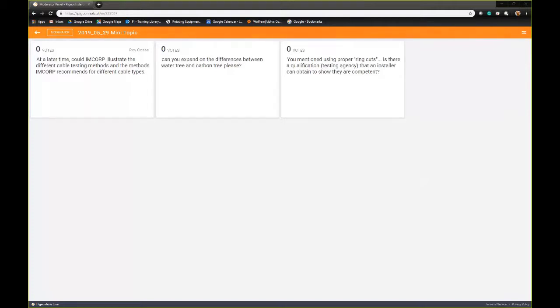In that 60-second time frame, we can capture all the information, a foot-by-foot profile of that cable, and tell you if it's good, if it's bad. We can even show you a prioritization list or the risk of failure for these particular cables. I hope that answered those questions. No, it did. Great job, Roy.